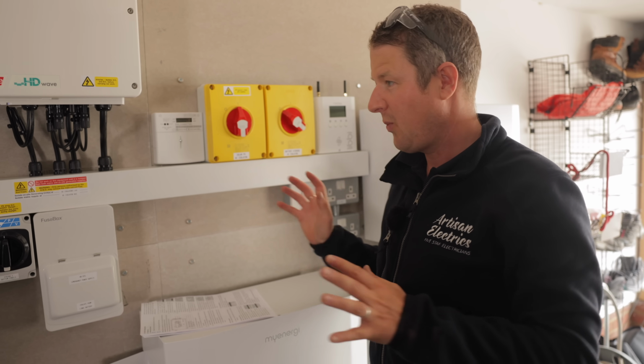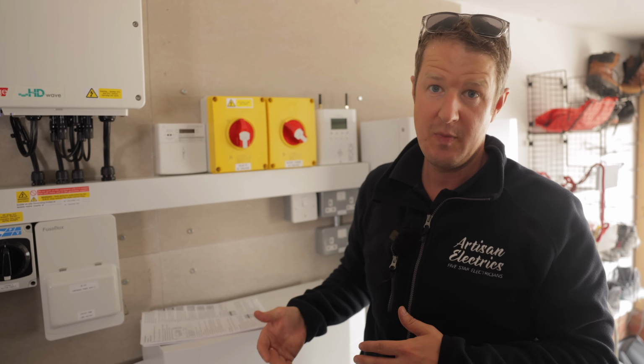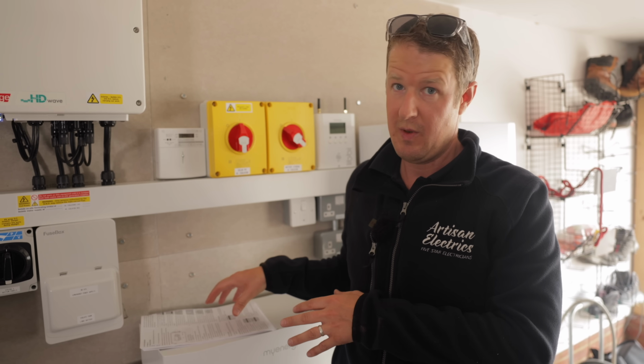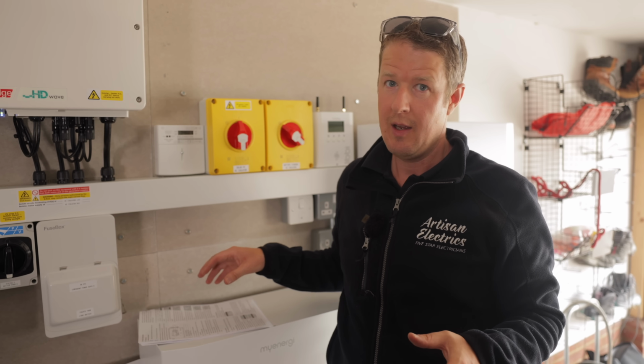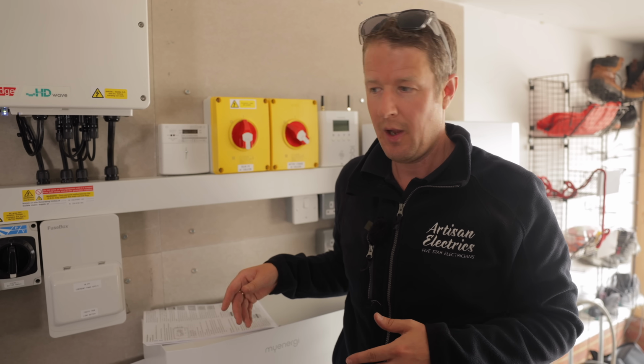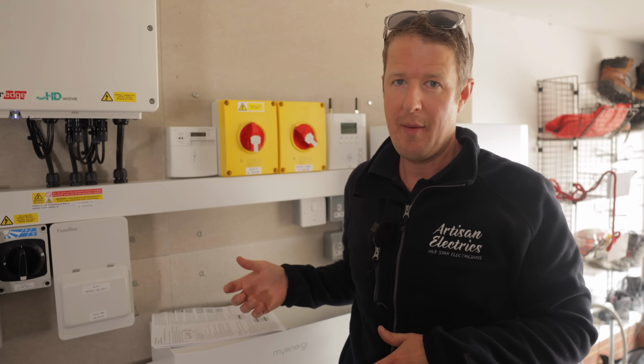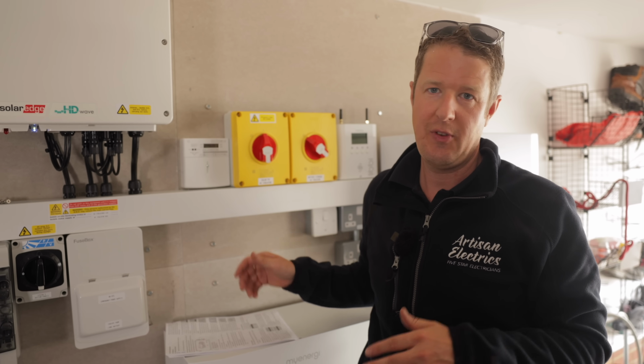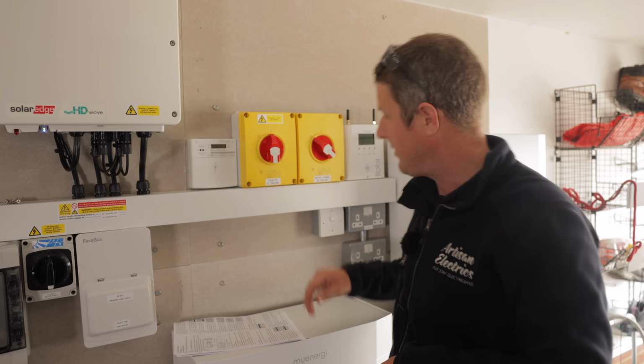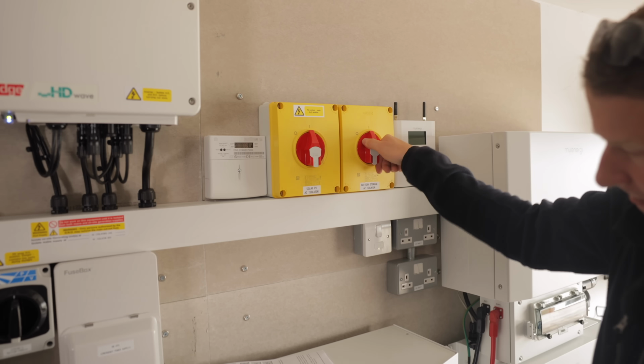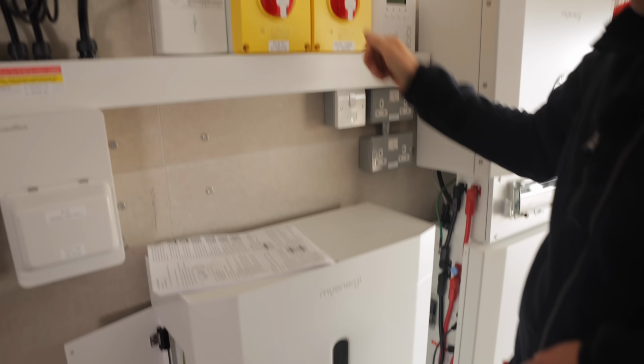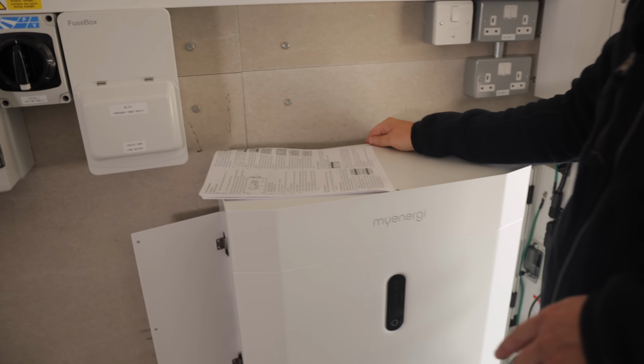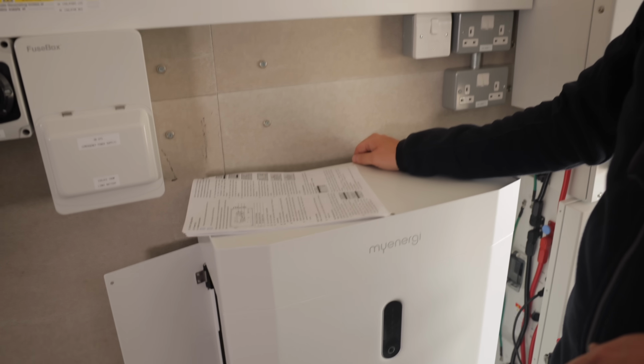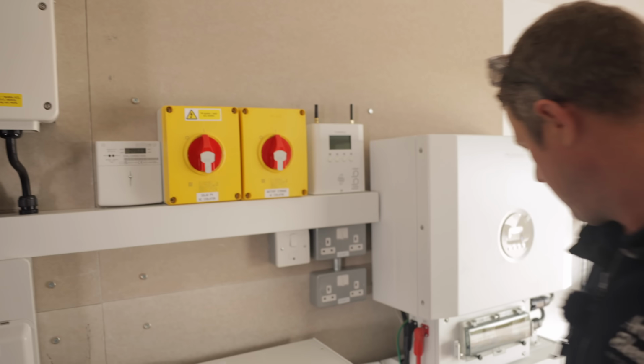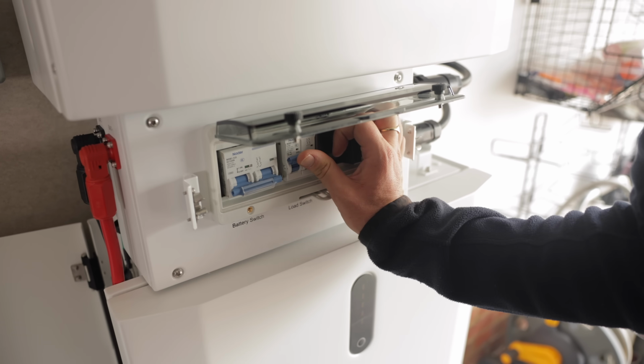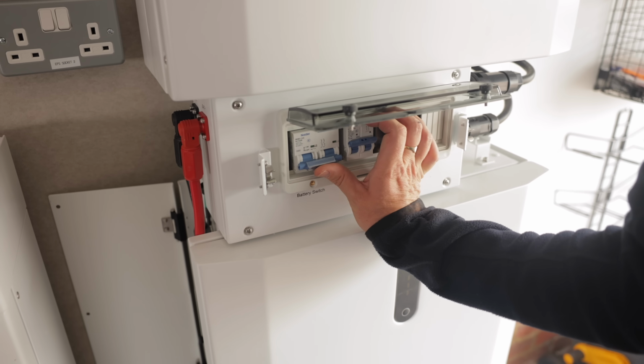So now that everything's wired up, there's a certain order in which we need to turn everything on, and I've got the instructions with me here to follow closely because, to be honest, it's not easy to remember the exact order. So if you're not sure, rather than risk damaging something by winging it, just follow the instructions. So the first step is to turn on our AC isolator. Then we're going to turn on the backup / load isolation switch if backup is connected. So that's this one here. Then we're going to turn on the battery switch, which is this one.